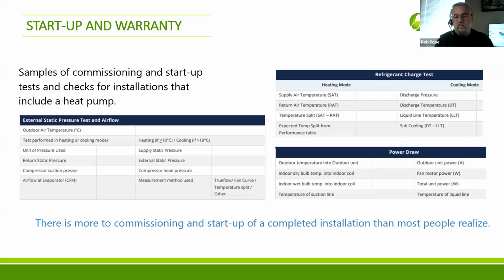So you can't just fire the thing up and be gone within 10, 15 minutes. There's literally hours of time that it takes to properly commission even the simplest system, a simple retrofit, for example. You can spend a day or two installing the system, depending on how easy or complex it is. But whatever system it is, even in a simple retrofit, you're going to spend a few hours, if you're doing it properly, commissioning the system and testing and checking everything.